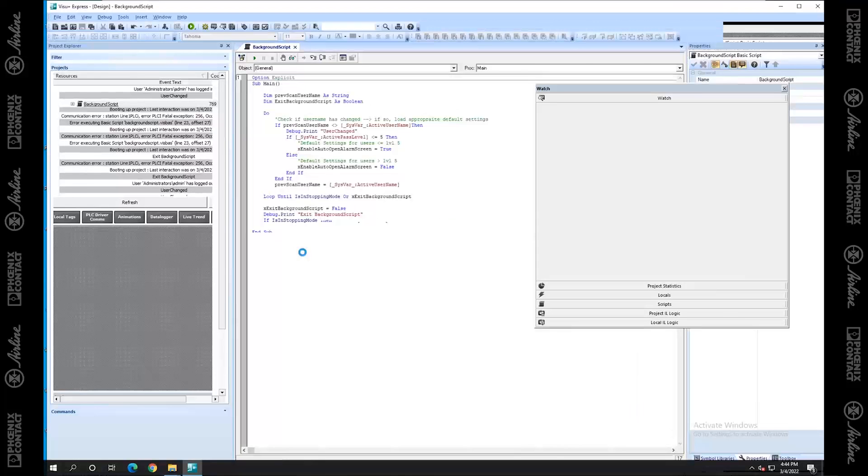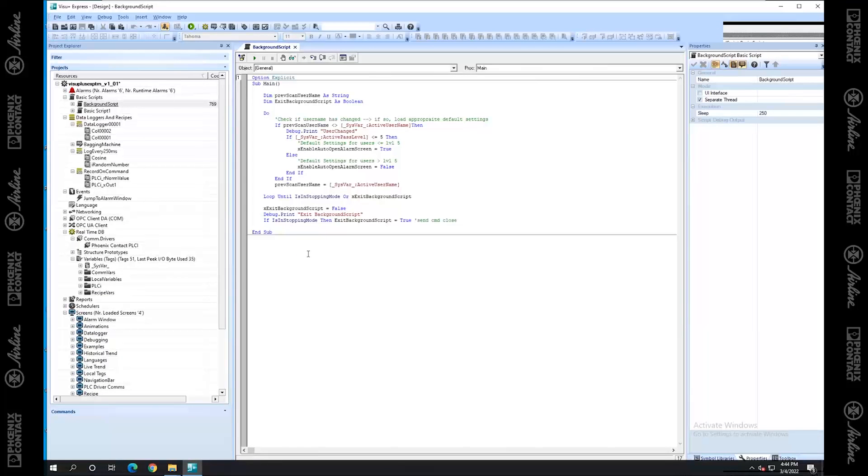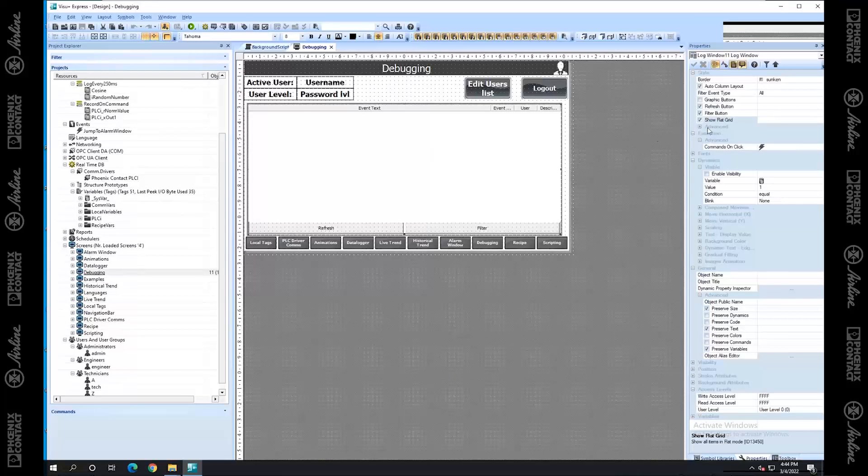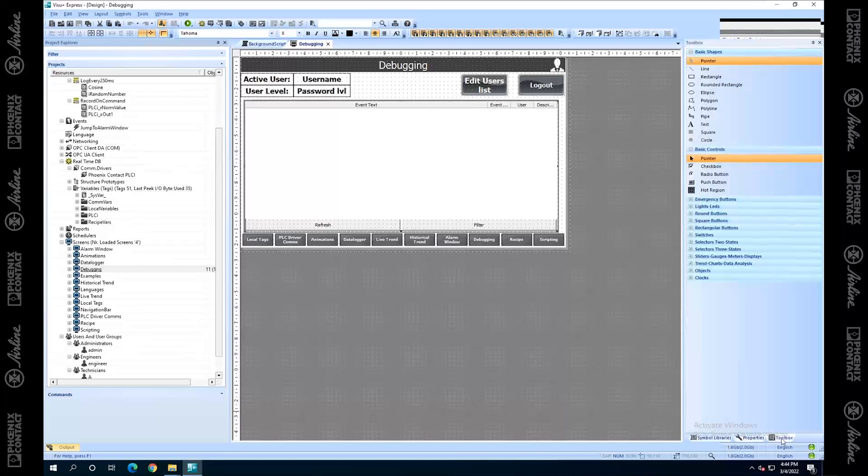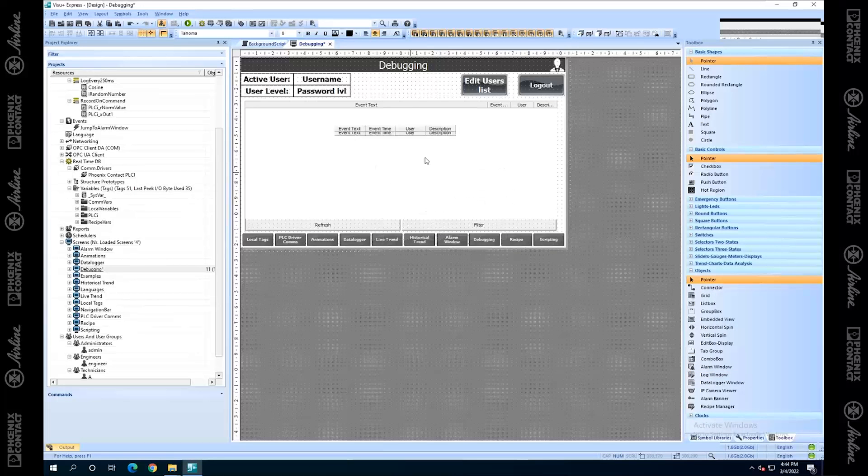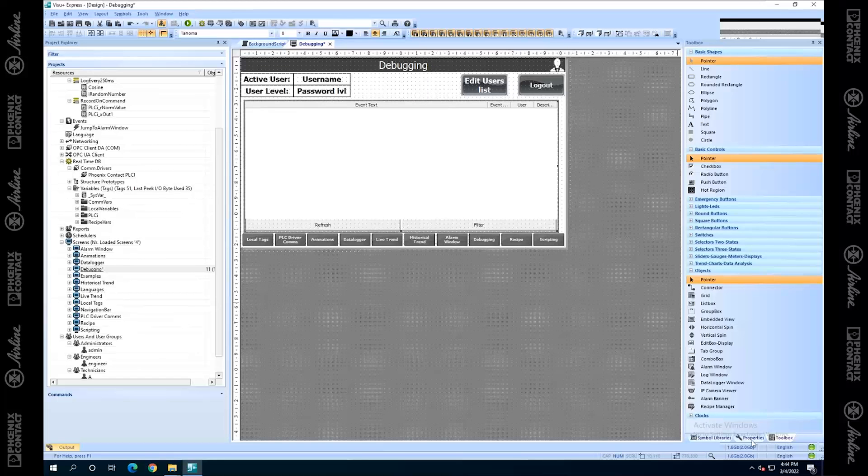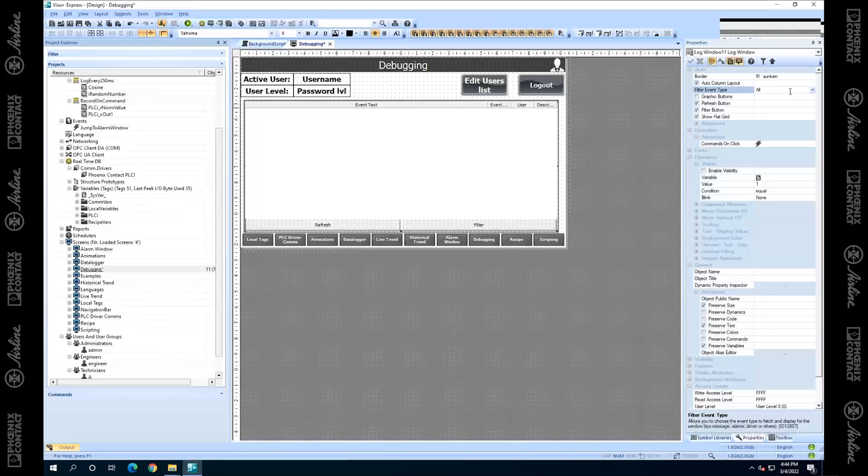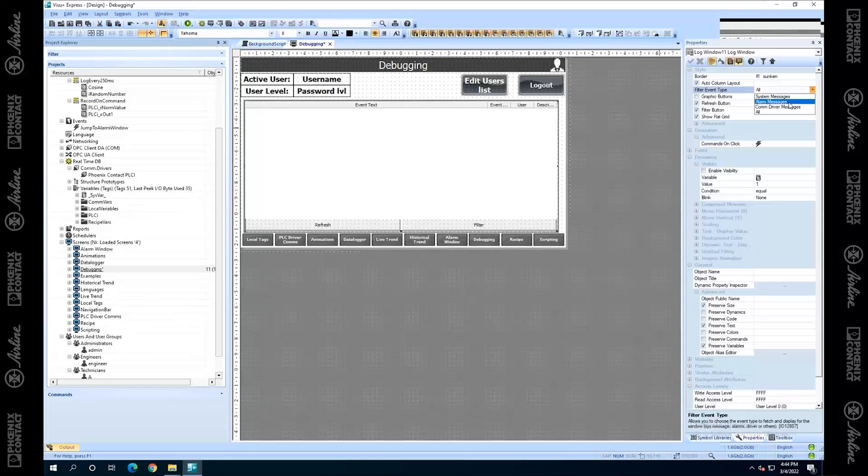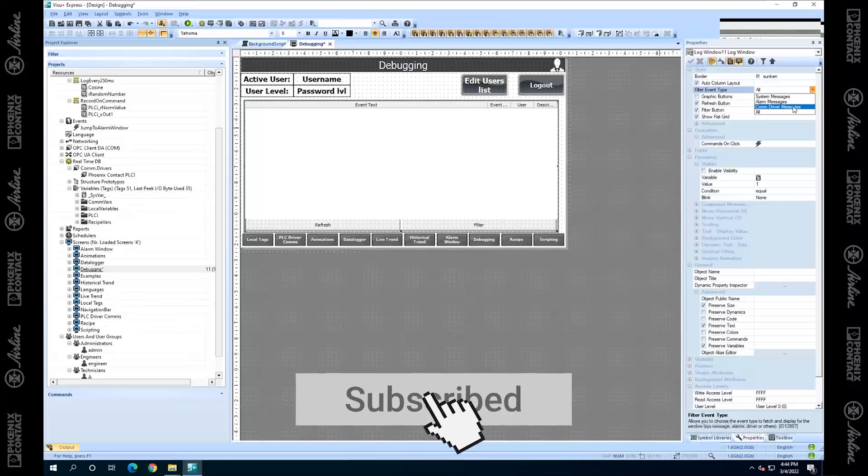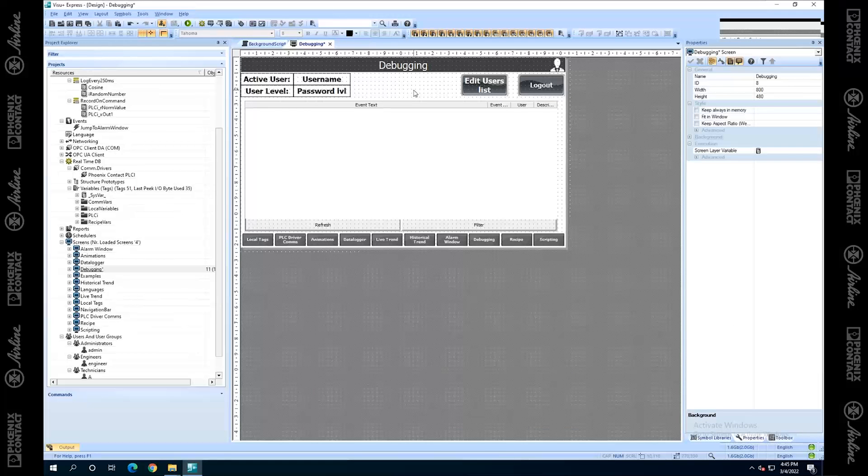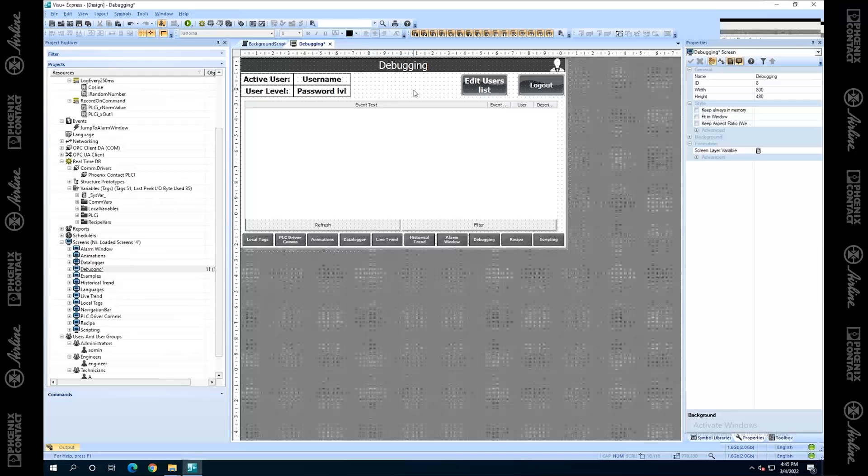I'll show you what that window looks like in the development environment and how to use that briefly. And then I think we've covered the majority of useful debugging tools. So let me show you that quick. Here it is. So this is the log window. If you wanted to grab it from here, it's under objects, log window. And there it is. But since I already have one on here, I'm going to delete that one. And then the properties over here, the properties of this log window, you can edit by event type. So like I was saying, it's showing all of them. You said, I only want to see my alarms. This is great for historical alarm management. You say, I only want to see my system messages. That's the output system messages in the system.log file that we were looking at earlier. I only want to see com driver messages. So I only want to know if I lost communications to my PLC. That's what this one is useful for. And then all is going to show all three. And that's really all there is to this log window. And I think that covers the majority of the debugging tips that I wanted to share.